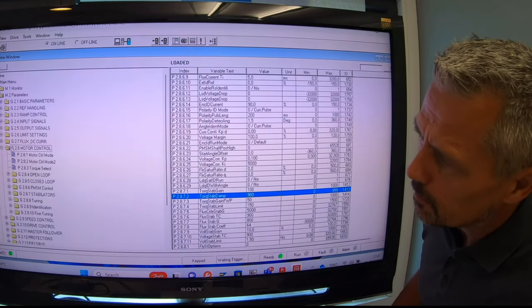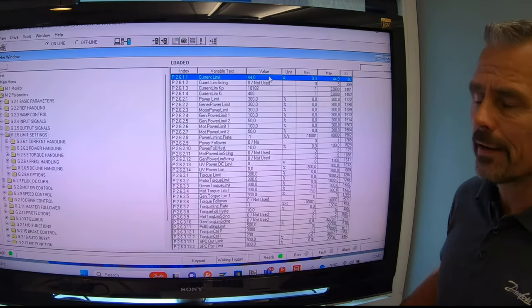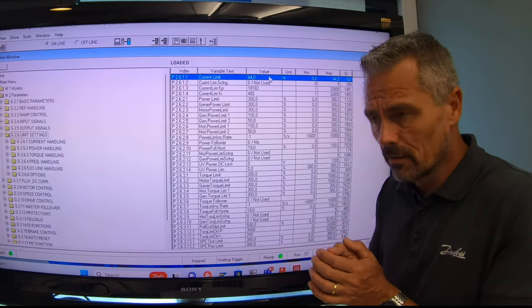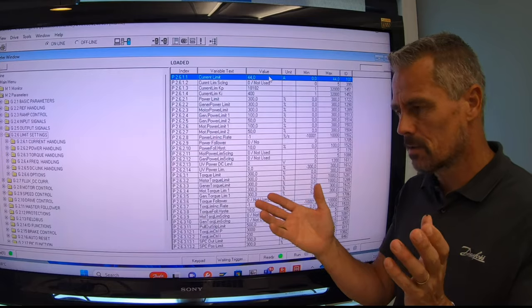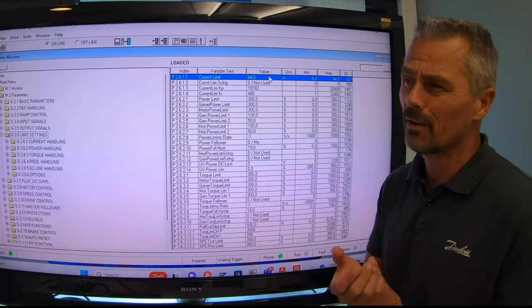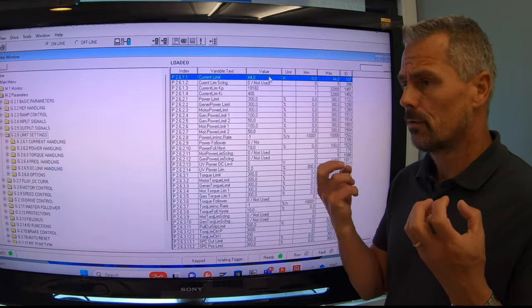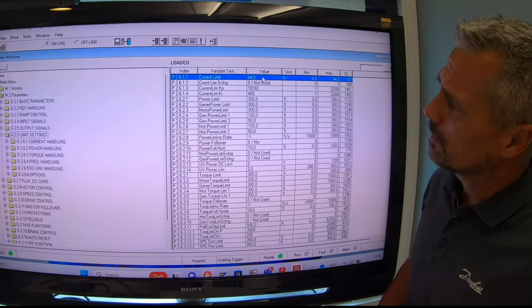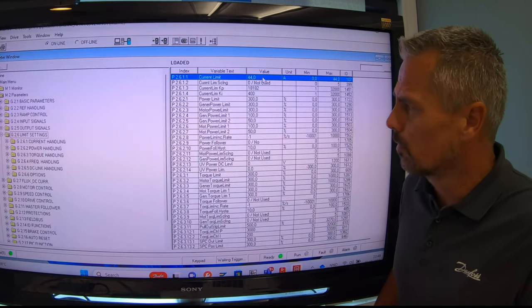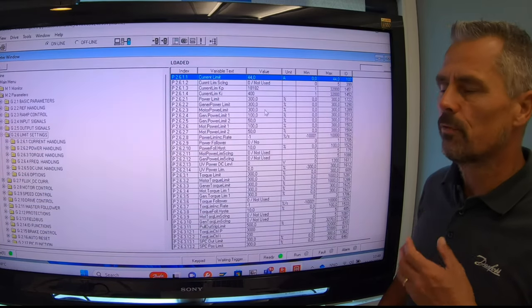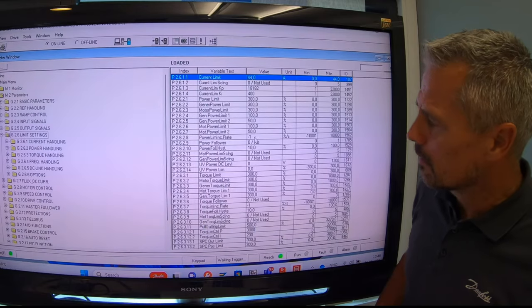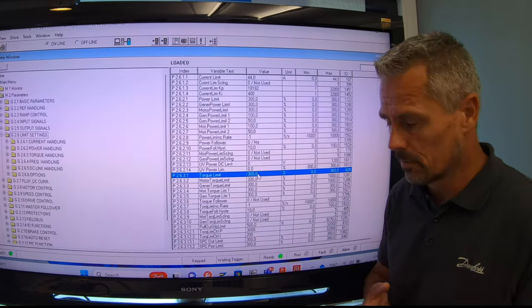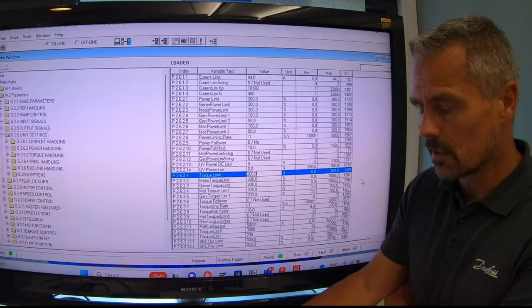When we do the tuning, I have now selected the highest current which my small NXP drive can give. The motor was 31 ampere, but I want more because I want the full nominal plus a good margin. So that the drive can give the reactive current during the identification runs. Also later when you run the motor, you want it to have some extra current to be able to give the reactive current for dynamics, for accelerations and stuff. So basically the current limit, you put it quite high, way more than the motor nominal. Because the real limits that protect the motor will be from the motor basic parameters.